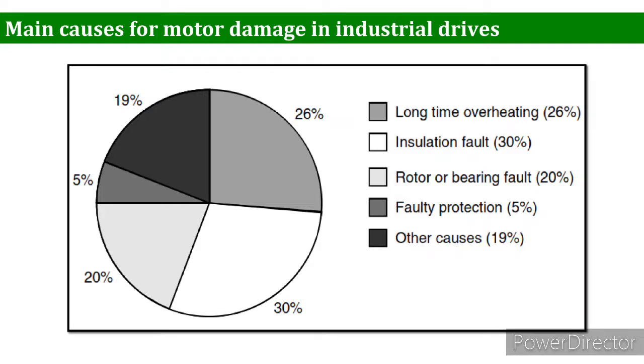Faulty protection — such as a wrong relay installed, a relay not working, or a faulty CT/PT — has a share of 5 percent. Other causes, including stator problems and winding problems, have a total share of 19 percent. This ABB Group statistics provides a clear idea of how important protection is and which areas to focus on.